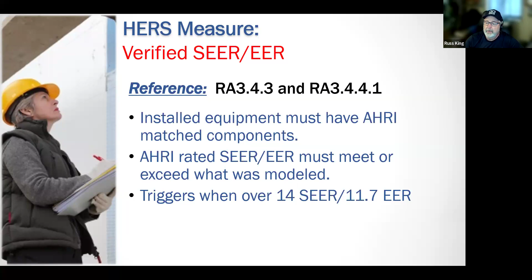All right. Heat pump heating capacity. This is going to be an even bigger deal. And the reason is that if you undersize a heat pump, it's going to run on the electric strips a lot more, and that's going to use a lot more electricity. So the compliance software will do a simulation and determine the minimum size heat pump equipment that won't excessively run on electric strips. Okay. And then the HERS rater has to go out there and check it to make sure that what they installed meets those requirements. Okay.